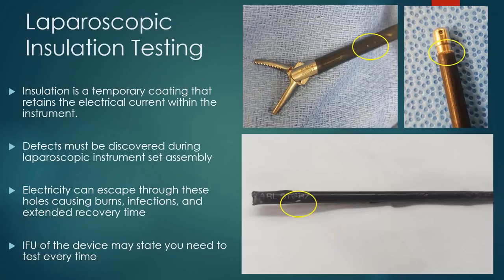Just understand that defects must be discovered during laparoscopic instrument set assembly, or depending on the type of insulation tester you have, it could have sterile wands where the checking is done prior to the procedure, and of course depending on your facility's policy.